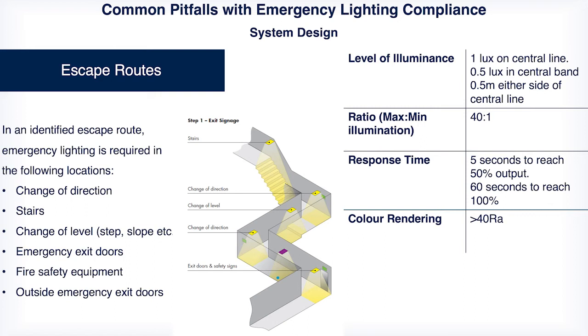an increase above 1 lux, and really that goes back to a point mentioned earlier, that it's often better practice to go above the recommendations rather than just hit them as a minimum, and that 40-to-1 ratio is in there to try and prevent people just complying with that 1 lux minimum.